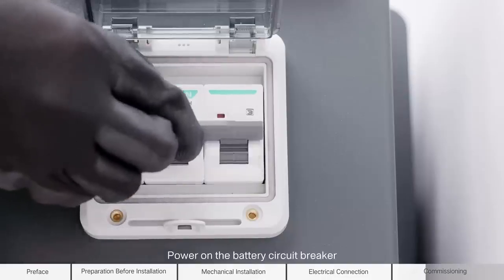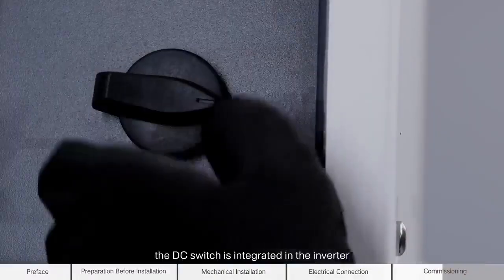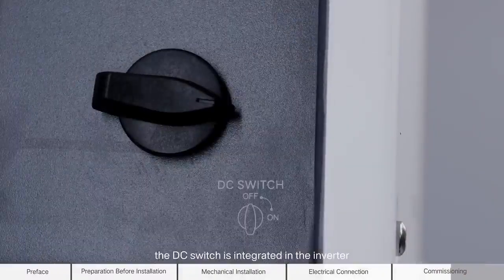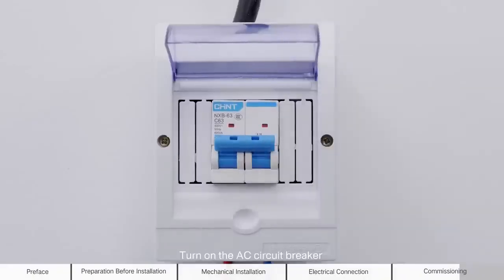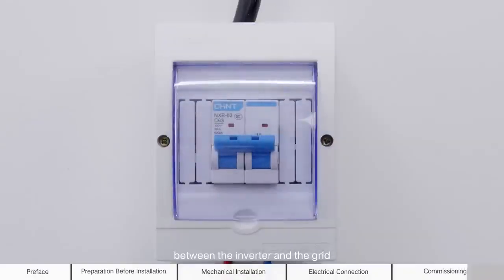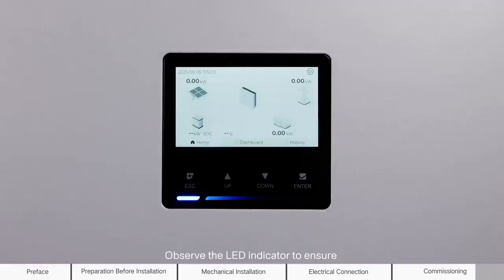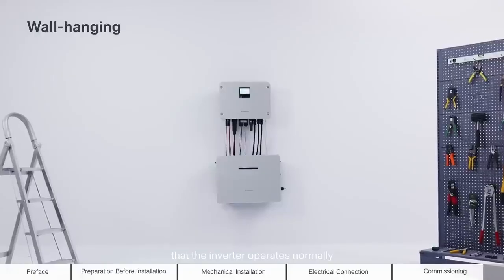Power on the battery circuit breaker. Rotate the DC switch to on. The DC switch is integrated in the inverter. Turn on the AC circuit breaker between the inverter and the grid. Observe the LED indicator to ensure that the inverter operates normally.